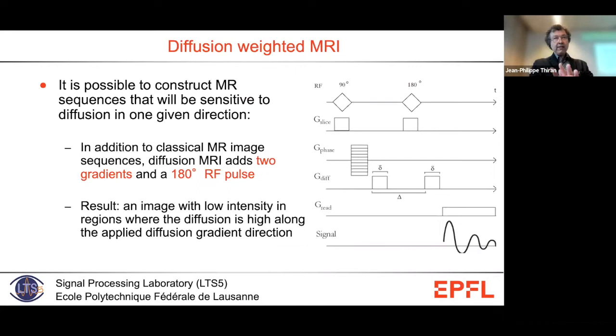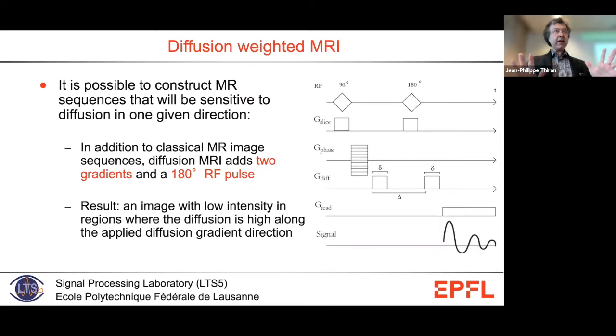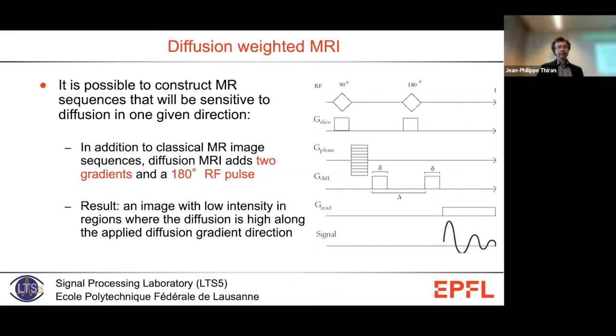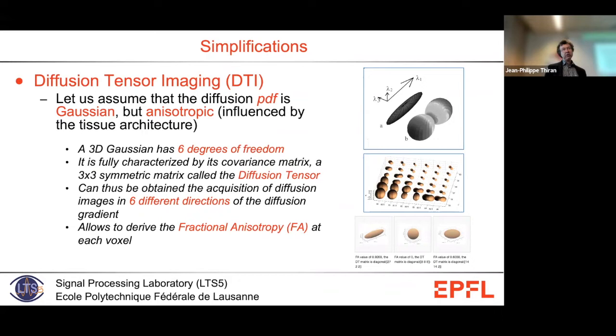At the end of the process, you see a net phase shift that makes all your spins at a given location much less synchronous. If they move in the direction you have set, you will see it. You can decide to measure everywhere in your volume whether there is diffusion in any direction by applying this gradient-and-inverse-gradient approach. To summarize: we get images that allow us to measure the ability of water molecules to diffuse in the direction we want, in every location of a volume.